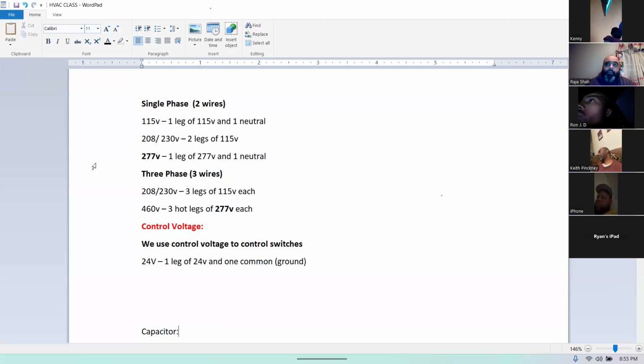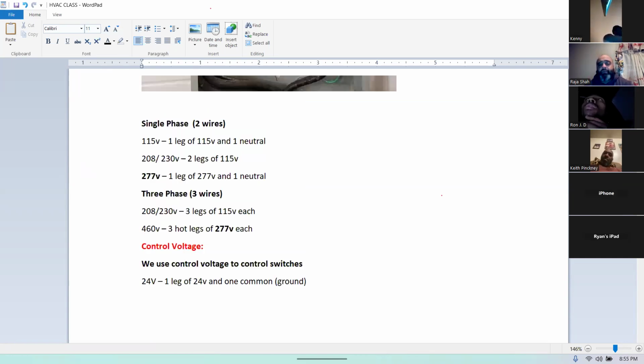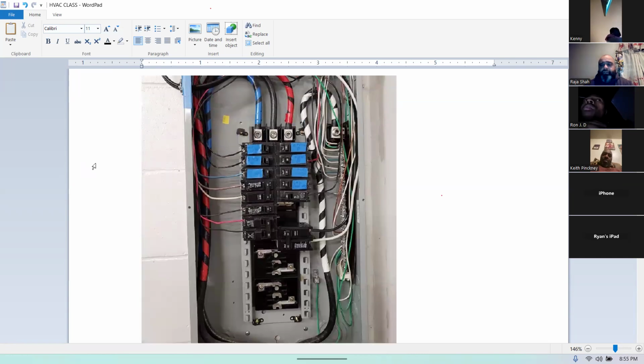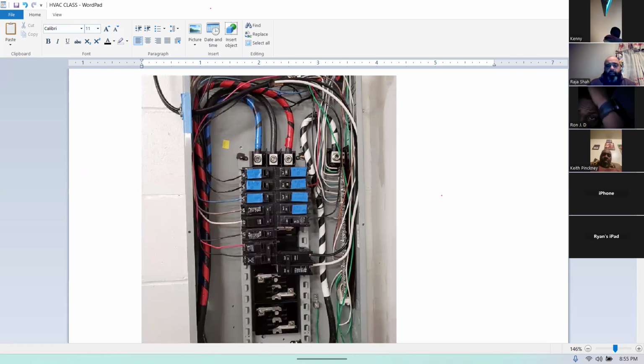Always check the phasing. Check which leg was which in 1, 2, and 3 in the disconnect box, then match it back to the contactor, so that 1 is still 1, 2 is 2, and 3 is 3. If the compressor isn't coming on, you want to make sure all your phasing is right. Look at your screen.